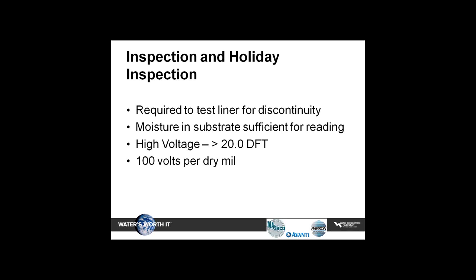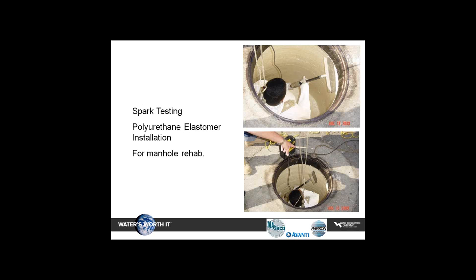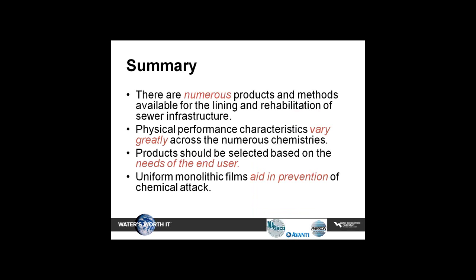When it comes to holiday inspection, I bring this up as a safety note. When talking about thick mil coatings — anything over 20 mils — you have to have 100 volts per mil, so we're talking about high voltage. Just be safe when using these tools. In summary, there are numerous products and methods available for lining and rehabilitation of sewer infrastructure. Physical performance characteristics vary greatly across various chemistries. Products should be selected based on the needs of the end user, and uniform monolithic films definitely aid in the prevention of chemical attack.